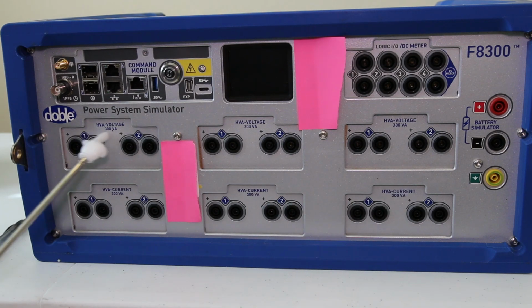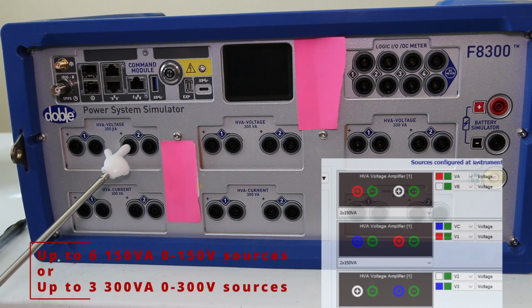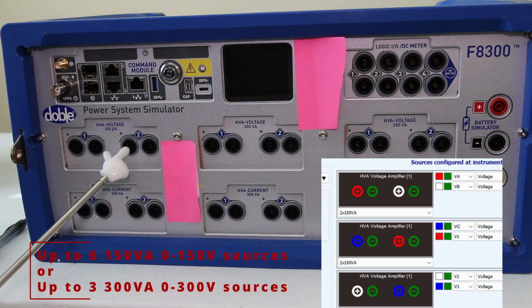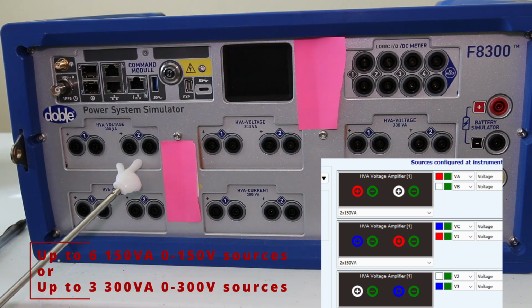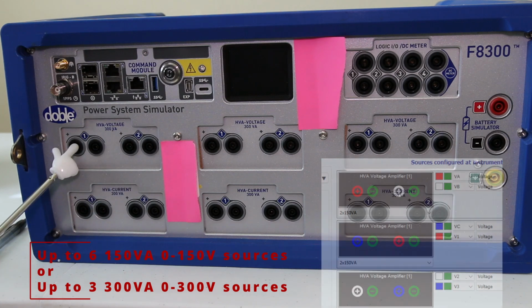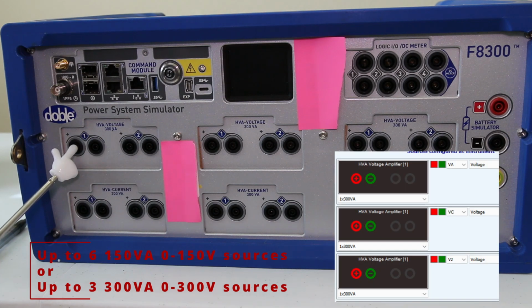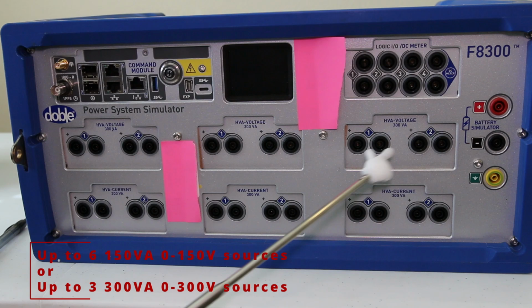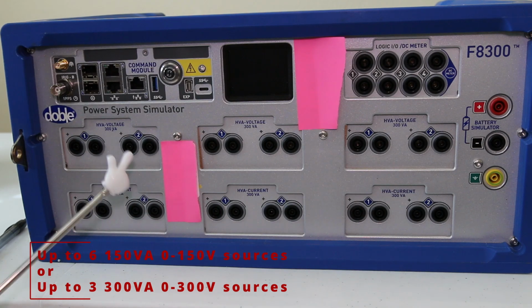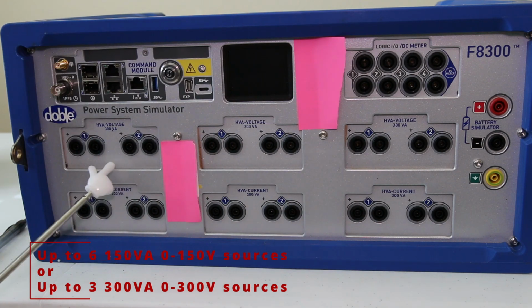On the HVA voltage modules, we can use either two 150 volt, 150 VA voltage outputs, or combine them, sort of like how we used to do on the 6150, using one as a single combined 300 VA, 300 volt supply. The way it's configured now, I can do 6 150 volt outputs at 150 VA each, or 3 300 volt outputs at 300 VA each.